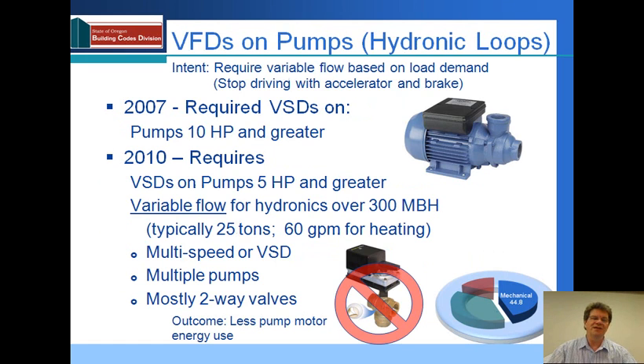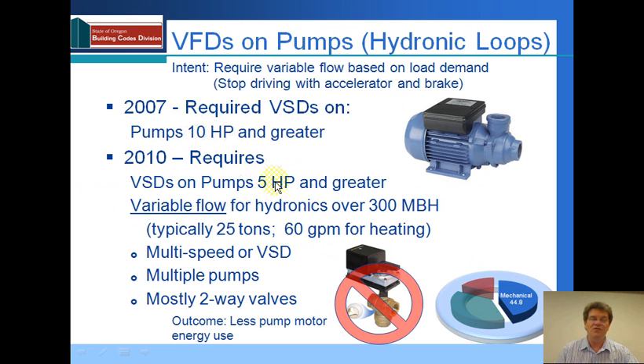Let's move on to the heating and hydronic systems found in complex systems. There's a reduction in the requirement for variable speed drives on pumps — it went from 10 horsepower down to 5 horsepower. That means any pump 5 horsepower and larger should have a variable speed drive on it.